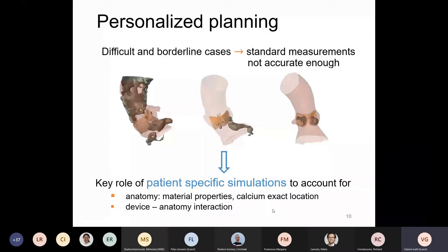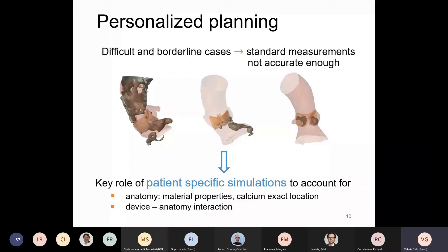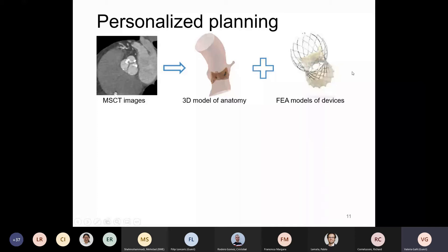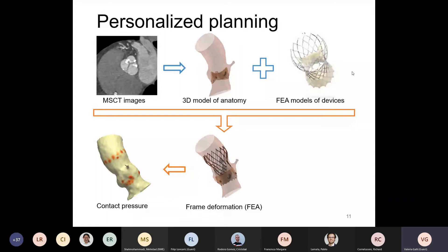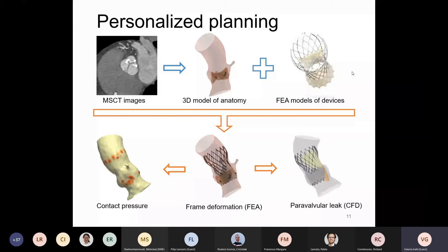The simulation takes into account the anatomy, the material properties of the anatomy, the calcium's exact location and its material properties, and most importantly the device-anatomy interaction. We start from CT images and build a 3D model of the anatomy — you can see the aortic root in pink and the reconstructed leaflets of the valve and the calcification in gray-black. Then FEA finite element analysis models of devices with material properties allow us to see the frame deformation inside that specific aorta. From this we can extract, for example, the contact pressure, which is very important relating to damage to the conduction system of the heart, and the paravalvular leak with computational fluid dynamics.